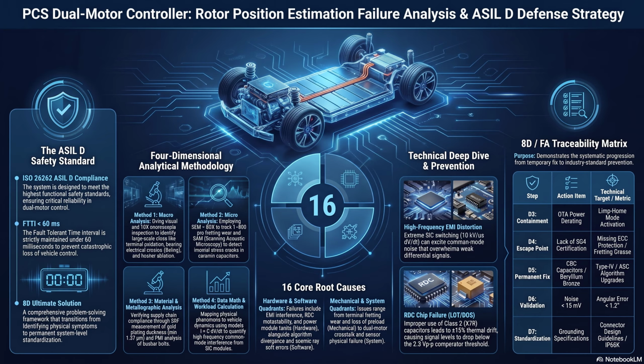And as the bearing geometry degrades, the rotor is naturally pushed eccentrically off-center. And an eccentric rotor warps the air gap between the stator and the rotor, which introduces spatial harmonics into the magnetic field. Right, which fundamentally distorts the resolver's angle reading. It is just a stunning cascade. Electrical noise causes physical machining, which causes magnetic distortion, resulting in a software failure. It's all connected. Which brings us to the next tribological nightmare on the list.